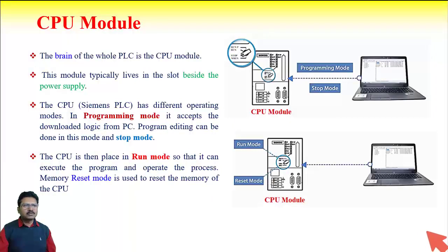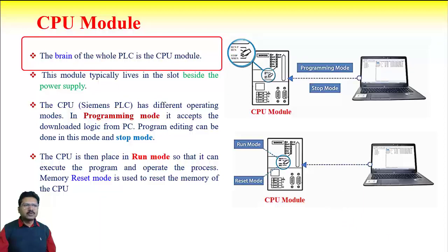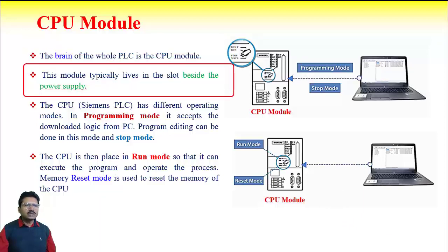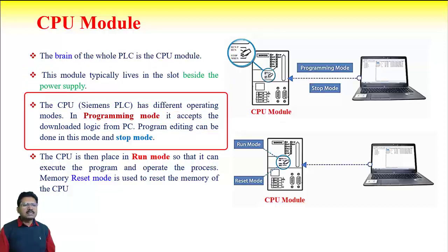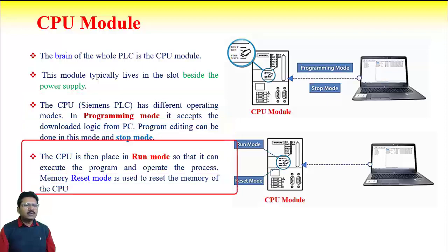The brain of the whole PLC is the CPU module. This module typically lives in the slot beside the power supply in older PLCs; nowadays any module can be placed anywhere. The CPU of the PLC has different types of operating modes. For example, in Siemens PLC the operating modes are programming mode, stop mode, and run mode. In programming mode, the PLC accepts downloaded logic from a programmer or PC. Program editing can be done in programming mode and stop mode. When we need to run the PLC, the CPU is placed in run mode so it can execute the program and operate the process. Memory reset mode is used to reset the memory of the CPU.